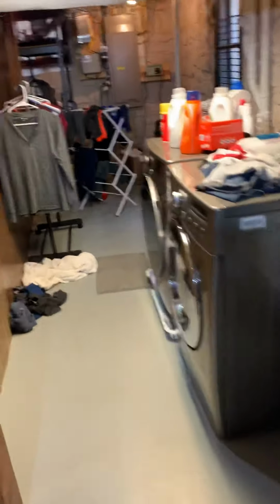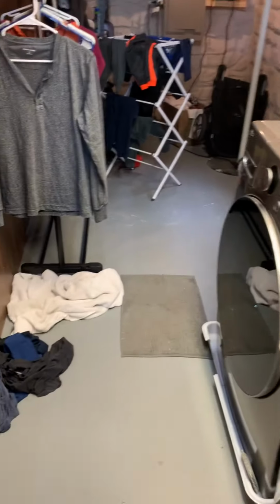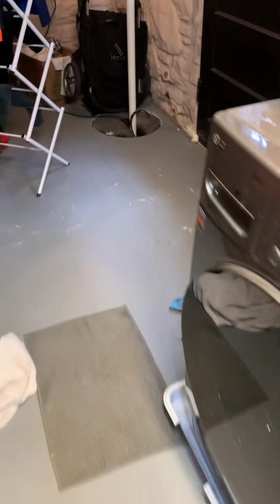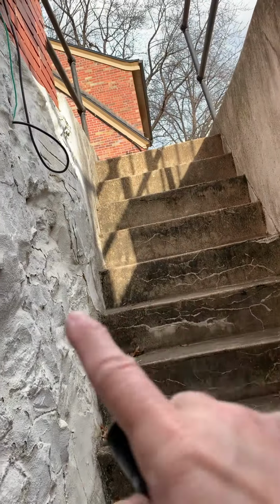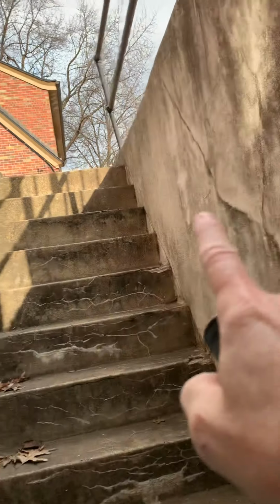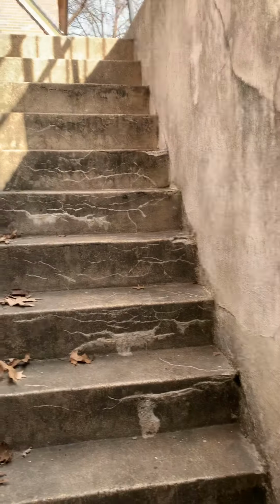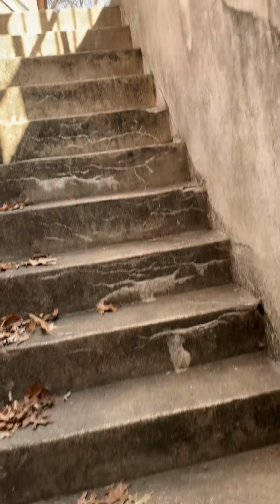And then as far as replacement and carrying the unit out, we would be looking at going out through here. We got about 3 feet in between the wall and the washer and dryer. Our narrowest point is coming up through these stairs. So we have to get into this little area, and then the bump out, so right about there to here is 34 inches. This would more than likely be a knockdown boiler. We'd have to knock down the one that's currently here and then get everything brought into here.